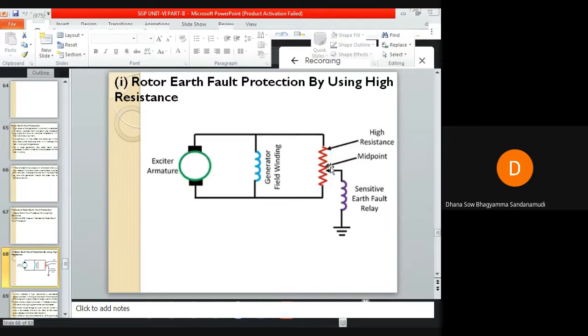In order to overcome this, we must shift this tapping point. Here it is center tapped, as I have shown you. If we shift the tapping on the resistor from the center to somewhere else, then the relay can detect the midpoint fault of the rotor. So this is one method of protecting the rotor against earth faults.